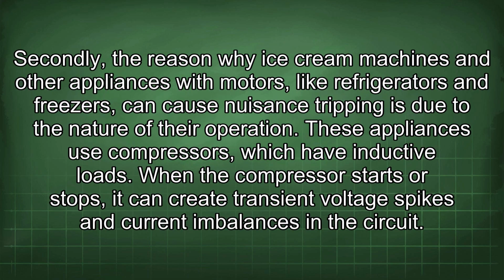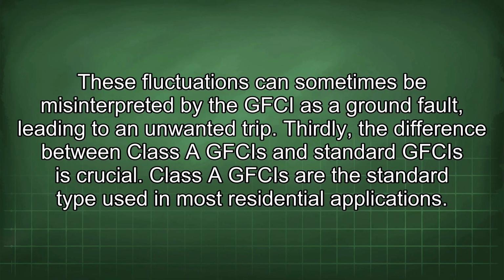Secondly, the reason why ice cream machines and other appliances with motors, like refrigerators and freezers, can cause nuisance tripping is due to the nature of their operation. These appliances use compressors, which have inductive loads. When the compressor starts or stops, it can create transient voltage spikes and current imbalances in the circuit. These fluctuations can sometimes be misinterpreted by the GFCI as a ground fault, leading to an unwanted trip.